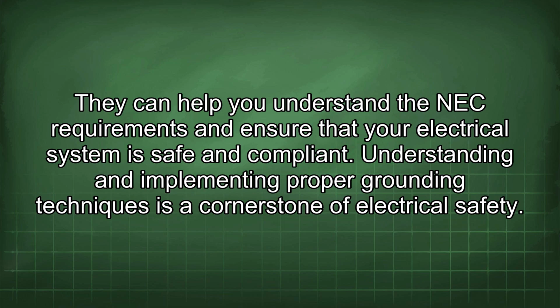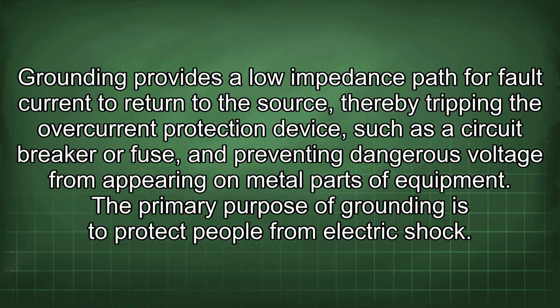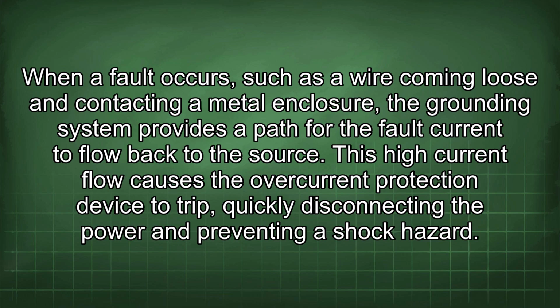Understanding and implementing proper grounding techniques is a cornerstone of electrical safety. Grounding provides a low impedance path for fault current to return to the source, thereby tripping the overcurrent protection device, such as a circuit breaker or fuse, and preventing dangerous voltage from appearing on metal parts of equipment. The primary purpose of grounding is to protect people from electric shock. When a fault occurs, such as a wire coming loose and contacting a metal enclosure, the grounding system provides a path for the fault current to flow back to the source. This high current flow causes the overcurrent protection device to trip, quickly disconnecting the power and preventing a shock hazard.